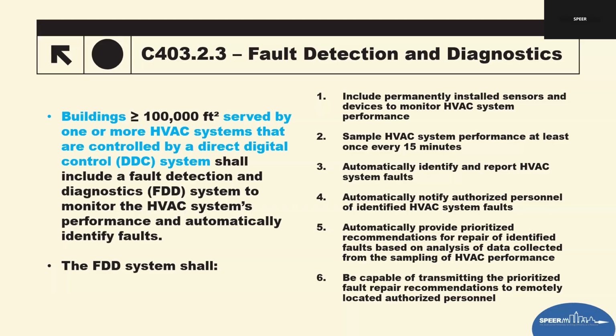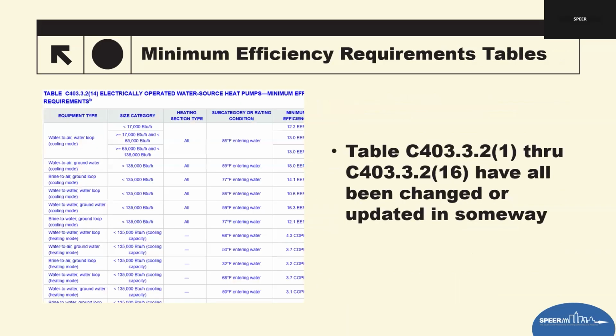Look for FDD functions in the sequence of operations, in the submittals and the control narratives, and how they're going to list all that. Make sure the submittals include sensor lists, training or trending intervals, alarm logic, notification pathways, etc. And then field inspection tips: check for those sensors that are installed and mapped to the BAS and FDD systems. Confirm trending sequence or frequency is every 15 minutes. So you should and could ask for a demonstration. Have them simulate a fault or review a test log to ensure notifications and recommendations work. Was someone actually notified when there's a fault that was pushed?